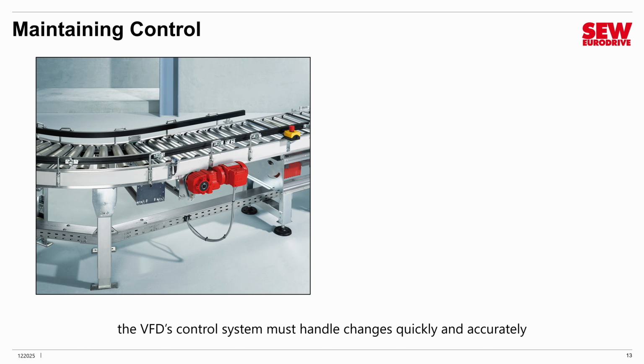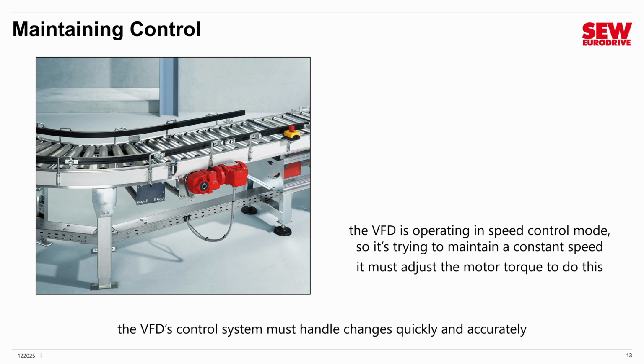It is running at a fixed speed that we have selected. We call that the set point. And the control system is simply trying to maintain the set point. It's trying to maintain a constant speed. The way it does this, it adjusts how much torque the motor is delivering.